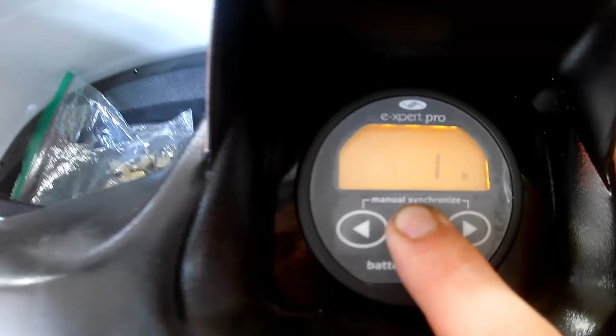The charge control indicator is on the front face of this box and is currently flashing green. How this charge controller indicator works is that the charge controller has its own built-in sensor that sends a signal to the LED, which flashes red when it's below 80% state of charge, yellow above 80% state of charge, and green above 99% state of charge. It's actually not very accurate, so let's look at the monitor on the top of this black box, which is a cheap Chinese-made battery monitor.